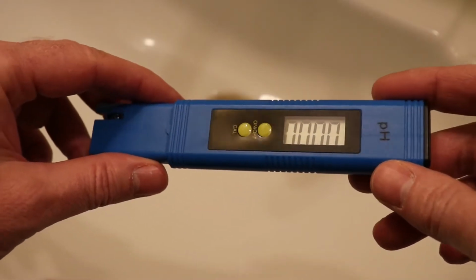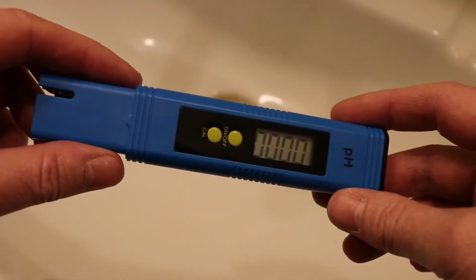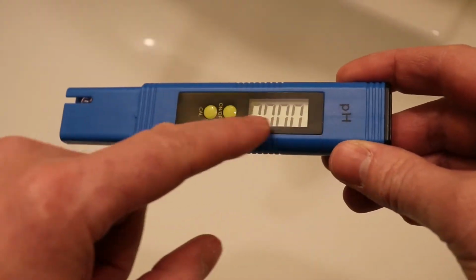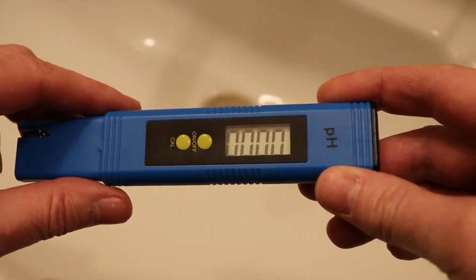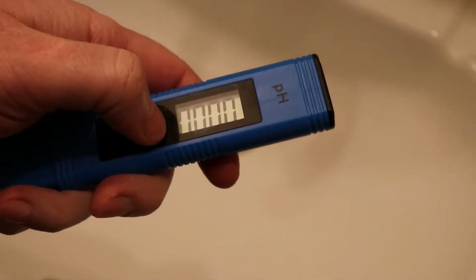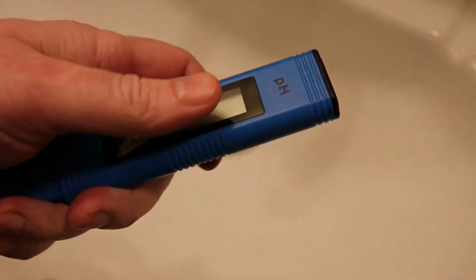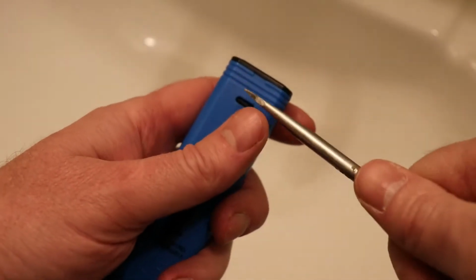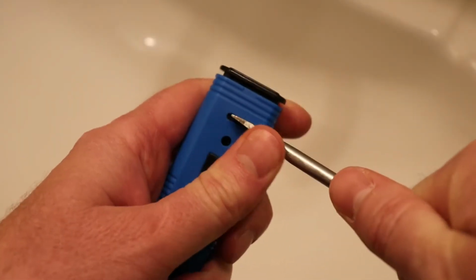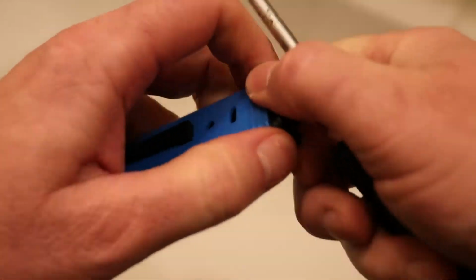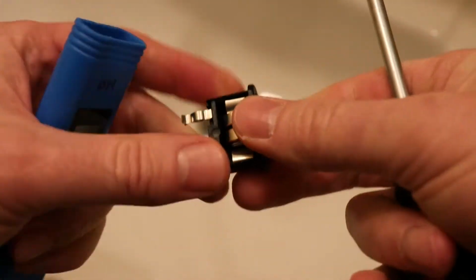So I'll show you how to fix these pH meters when you get an error code when you're trying to calibrate these in the calibration solution. First, power it off by pressing this button, flip it over, take a screwdriver, pry this little tab up there, and take these batteries out.